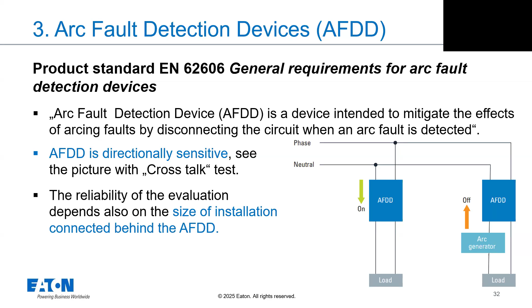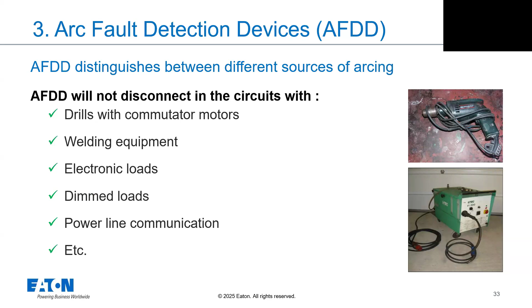But on the other side, we have no problem with standard loads where some higher frequencies are generated. The AFDD is able to work properly without unwanted trips. It means in the memory of the AFDD is fixed, for example, the spectrum of signals from some devices, a welding machine or drill machine or what else, electronic loads, dimmed loads, and so on. This is acceptable for the work of the AFDD. Even if we have such an arc from the commutator of a motor, it's ignored because it's known.